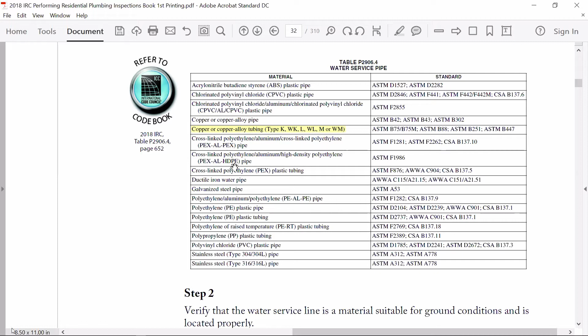Is it waste? No, that's a good guess, though. No. It's weight. It would make sense that it would be for water, right? But it's not. So, weight. There are two ways to manufacture pipe. One is what we call an extruded means, where we take a rod and run it through a mandrel, and it just extrudes, pokes a hole right through a solid piece of material. The other way is what we call welded seam pipe, where we use plate, ladies and gentlemen, wrap it around a mandrel, and then weld it longitudinally. It's called welded seam pipe. You see what the W stands for now? Welded seam K copper, welded seam L copper, and welded seam M copper.